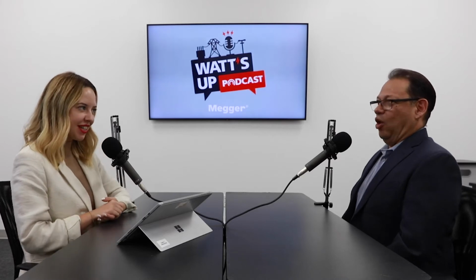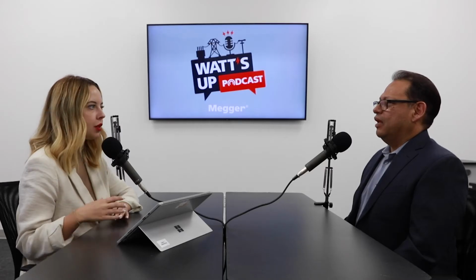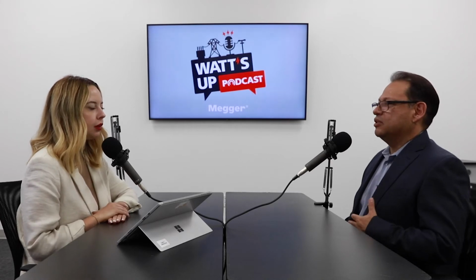Integrity is a strong word, and I'm going to use it, because integrity has to be taken care of from day zero, when you start designing this power transformer, when you go into the mechanical, the dielectric, the electromagnetic, and the thermal characteristics. It's the whole view you're taking into account. Absolutely, you cannot leave little points outside of your equation. Everything has to be in.